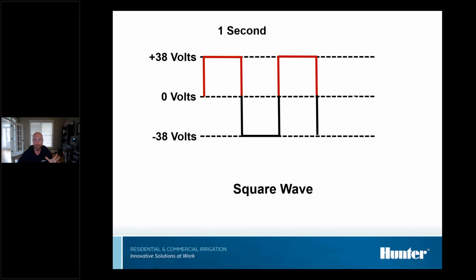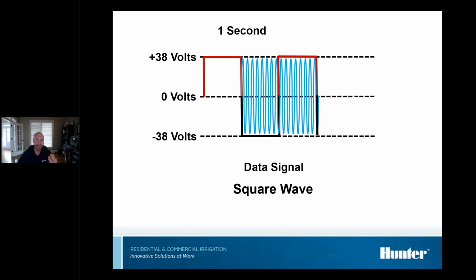Now why is that important in a two-wire system? That's because we send data in between those pulses to tell certain stations to turn on. We send data that gives flow data back to the controller. We send data that tells if a rain sensor is coming on and off. So embedded within those pulses is data. Real important to understand that concept.